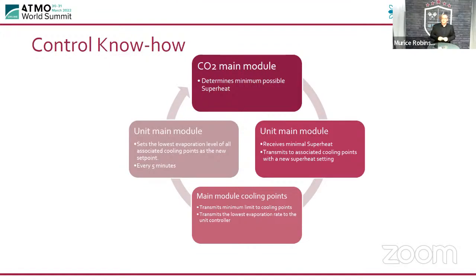The nice thing about this is that the system is always fine-tuning itself. With a normal system, you install it, it's working, and you can walk away. And within a year or two, after you've had 20 mechanics through there doing their little intelligent part that they feel is better for the system, you end up with a system that's not fine-tuned anymore, and it's not running as well as it could. Whereas with EVALIFT, it's always trying to find its perfect conditions. So it's fine-tuning itself.